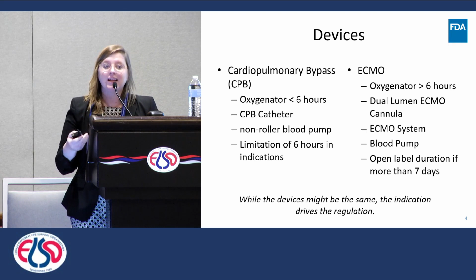And then we have to get a little more complicated because ECMO was reclassified in 2016. And so what this means is it used to be Class 3 and you would need a PMA. And then in 2013 and 2014, FDA convened 2 panels that evaluated the data that was out there. And ultimately in 2016, we came out with the outcome of that final order. And we decided that there was enough information that components or systems indicated for patients with acute respiratory failure or acute cardiopulmonary failure where other available treatment options have failed and continued clinical deterioration is expected or the risk of death is imminent would be a 510K for ECMO.